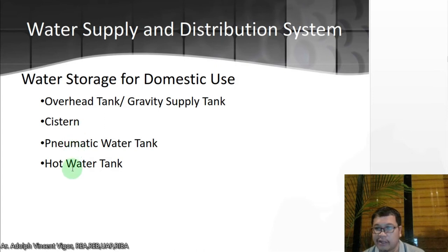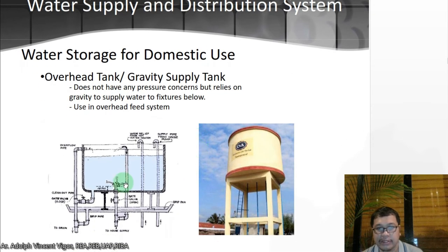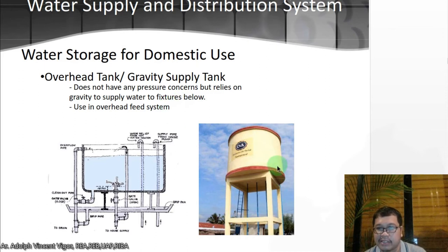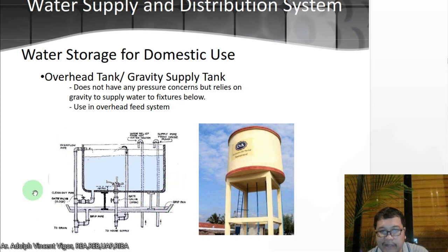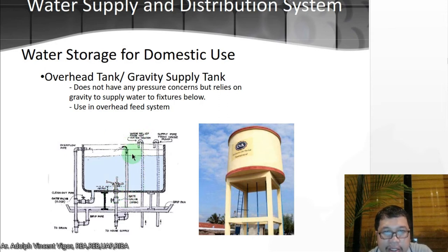You also have the pneumatic water tank and the hot water tank. The overhead tank or gravity supply tank does not have any pressure concerns but relies on gravity to supply water to fixtures below. It uses an overhead feed system. It has an overflow pipe — when the water reaches a certain level it drains. It has an in-house supply line and a ball valve to let water in, plus a drain valve and a drip pipe in case of spillage.